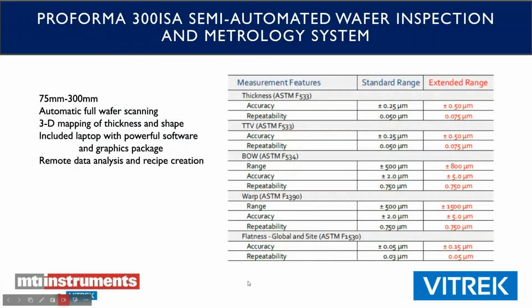The 300 ISA is our semi-automated inspection system. It does accommodate wafers between 75 millimeters and 300 millimeters. It does automatically scan your entire wafer, and it will give you a 3D map of your wafer for thickness and shape. So that includes, as you can see, thickness variation, bow, warp, flatness. There's a couple other things in there that if you need more information, I'd be happy to share with anybody. But again, in standard range, it gives you accuracy to a quarter micron with a 50 nanometer resolution.